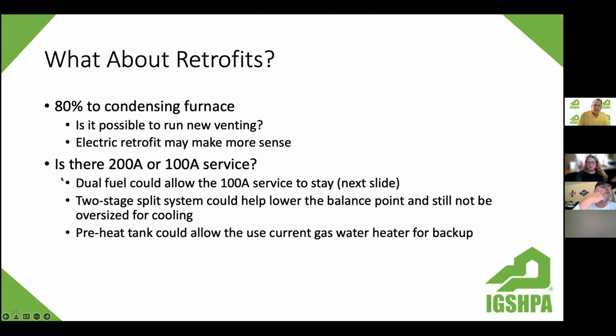I touched on this a little bit. The 200 amp service might need to be upgraded to a 400 amp, but here's sort of the opposite situation. Suppose on a retrofit, they only have 100 amp service. Well, even geothermal might push them over the limit with that backup electric heater, or converting to an electric water heater, or what have you. So we might want to look at some dual fuel options. I have a slide coming up that shows some options there that aren't looked at very often.